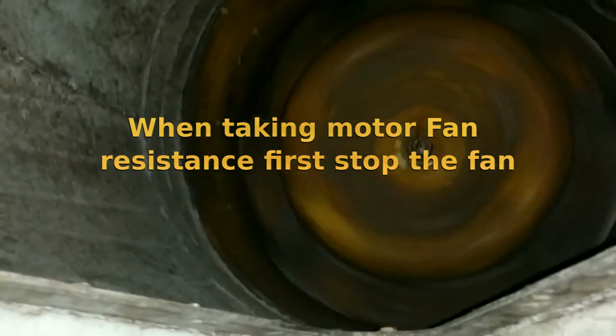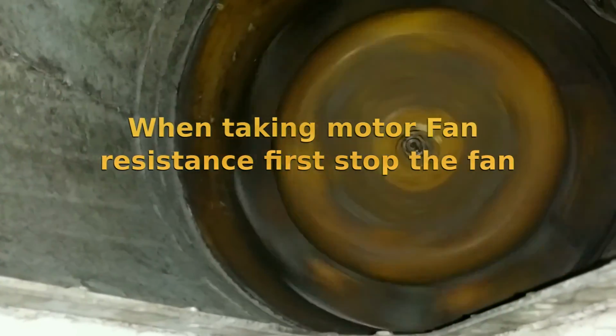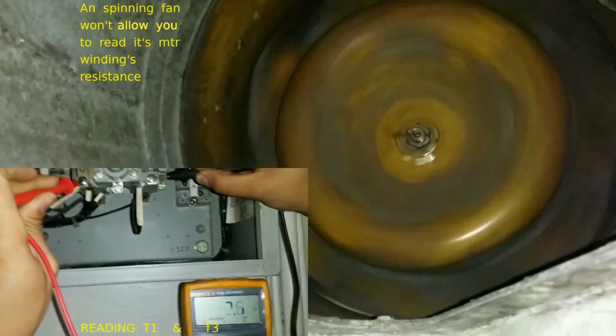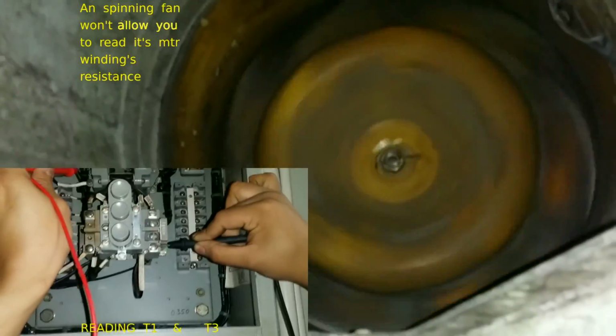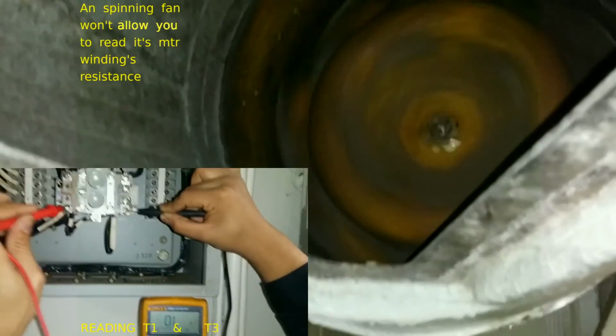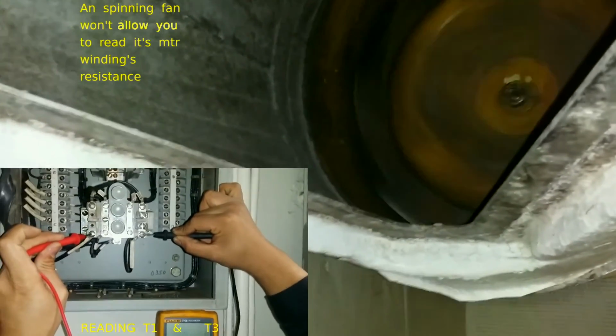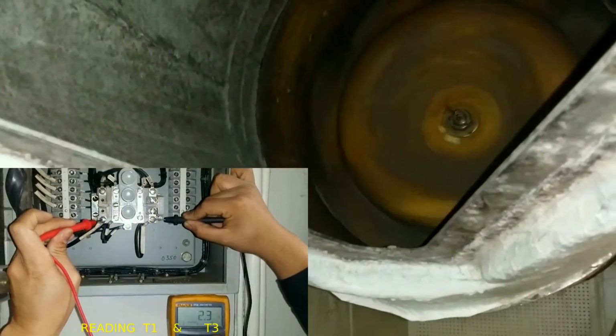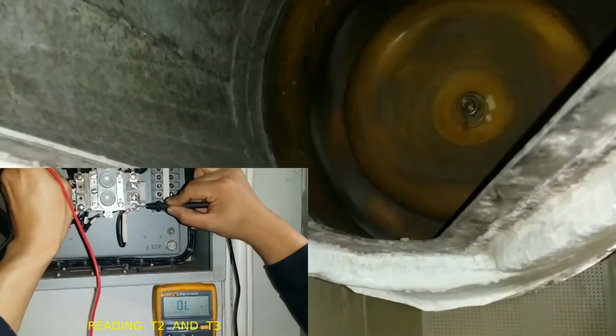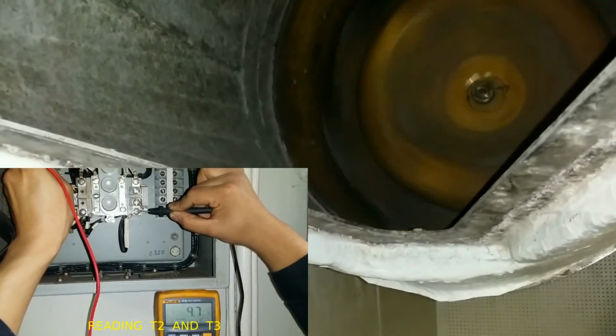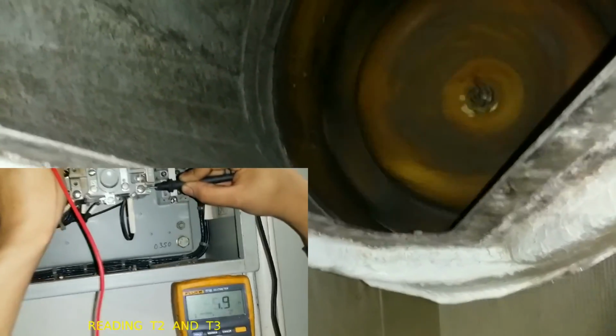The exhaust fan of the space is working, so it's drawing air to the point that this fan is free spinning. So whenever I try to do a resistance check, I won't be able to read if this motor is good or bad. I will have to actually physically stop it and put a brake on it, something to stop it, so that I can actually take a good set of readings on that.